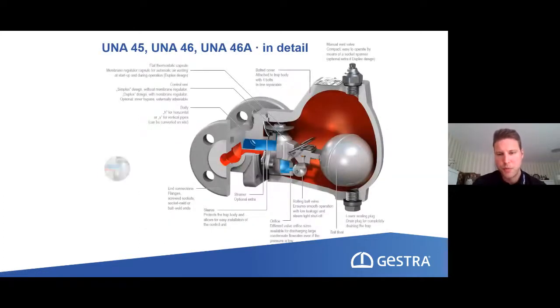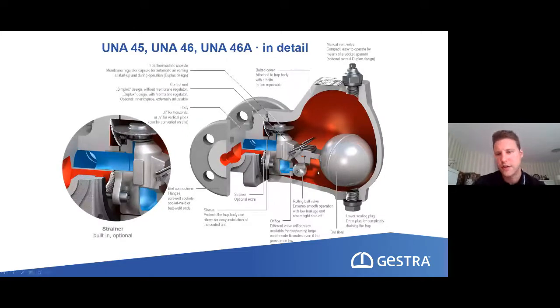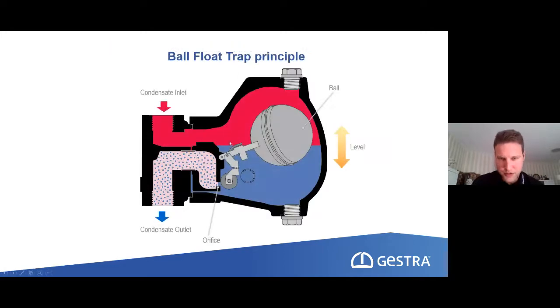Yeah, here's some more details about it, and I have to tell you what the two basic requirements are that we have on a steam trap. So the first one is we have to discharge condensate without losing live steam. So this is what this kind of control unit guarantees. As soon as we have the water lock here, steam cannot leave the steam trap. But the second basic requirement was the automatic air venting. And as you can imagine, air venting is not possible if we take a look at this kind of design here, because the air will always stay above the water line and cannot be discharged.